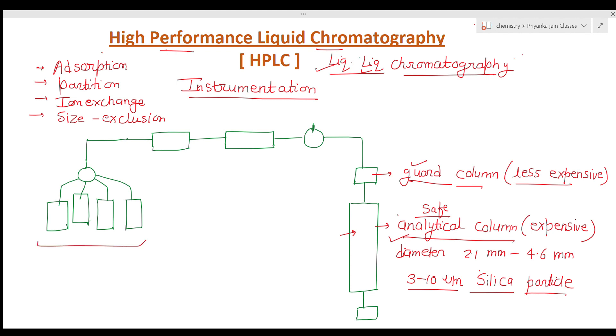Now, this is the solvent reservoir — a specific feature of HPLC instrumentation. We use several solvent reservoirs to allow changing the mobile phase composition, especially when using gradient elution. Before use, the solvents must be treated to remove dissolved gases such as O2, which can produce bubbles and interfere with the separation.